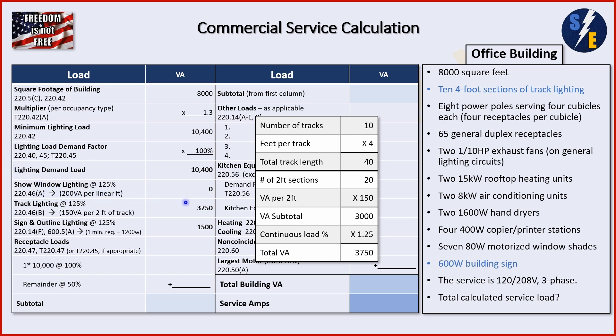Now we move into specialty lighting. We don't have show window lighting, but we do have track lighting — ten four-foot sections. Per 220.46B, track lighting is calculated at 150 VA per two feet of track. Ten tracks times four feet equals 40 total feet, divided by two gives us 20 two-foot sections. Multiply by 150 VA and we get 3,000 VA. Because this will likely operate for more than three hours at a time it's a continuous load, so we multiply by 125%. 3,000 times 1.25 equals 3,750 VA for track lighting.